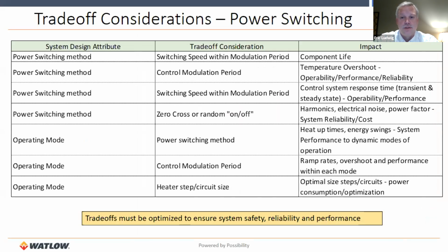So again, another chart here full of words, and I won't cover all of these, but these are just some of the trade-off considerations when going through and understanding the power switching technology that you'd like to use. A lot of it is based on what we call a modulation period. So that's the period, you can think of that as the total time that it takes to cycle something on and off. So an on period plus an off period would equal your modulation period. And the longer that modulation period becomes, the more time that you can potentially have your heater on or off within that time. But that also then impacts the overall life in the temperatures that heating element is seeing. So a lot of this power switching method up here has to be considered with the modulation period to understand the total life of the system, the operability of the system, and then just your control system response time.